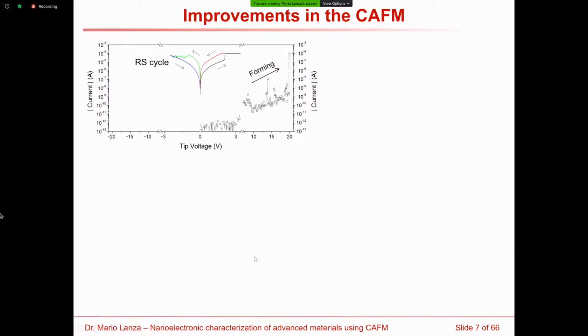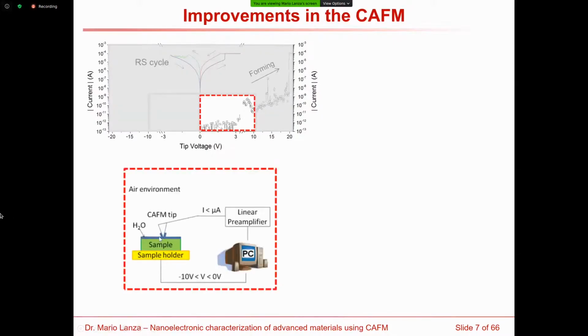You can see here the block diagram of a standard conductive AFM. And this is the window that you can measure. You can only measure currents up to some nanoamps. You can only apply voltages up to 10 volts. And you cannot measure both polarities, because if you are measuring in an air environment, you have a water meniscus between the tip and the sample. And you can induce local anodic oxidation if you inject electrons from the tip. This is a problem of chemistry, but this is very well known in our field.